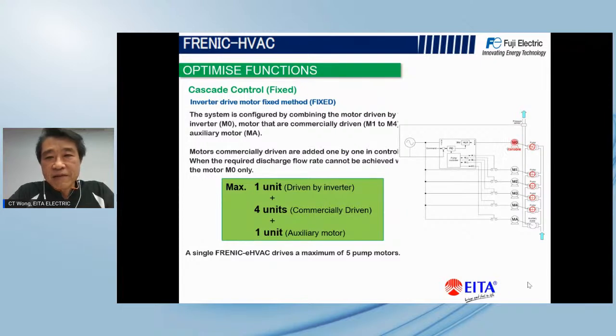So the pump speed is varied. If the inverter runs to maximum and still cannot fulfill the demand, the inverter will automatically call M1 to come in. And if it is still not enough, for example the demand is 4.5 bar, then maybe you have to run all 5 pumps and vary the M0 pump to half in order to get 4.5 bar. So this is what we call the fixed type.